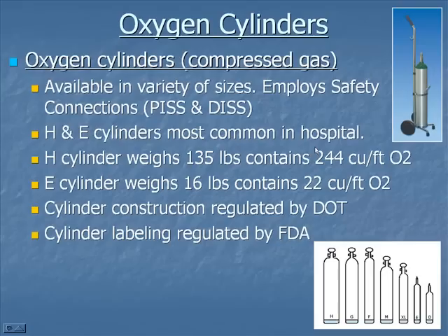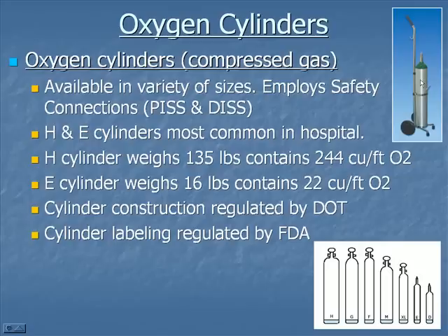The liquid is vaporized to a gas, reduced to a pressure of around 50 psi, and fed into the hospital piping systems. Oxygen cylinders are compressed gas available in a variety of sizes. They typically employ safety connections — PISS and DISS.